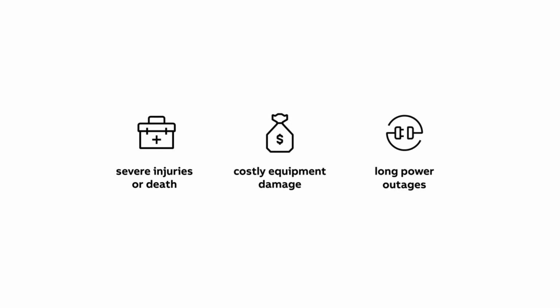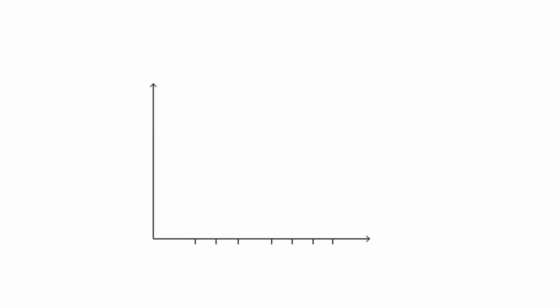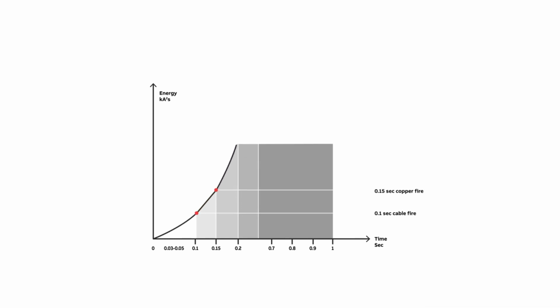and power systems. An arc flash can lead to severe injuries or even death, costly equipment damage, and long power outages. The main parameter of the electric arc, which characterizes its destructive ability, is incident energy. This is directly proportional to the arc duration and arc current. Without any active arc flash mitigation solutions in place, the arc clearing time may vary from 0.2 to 0.4 seconds. Within this short time, cable, copper, and steel can burn, melt, and vaporize. Therefore, it is of utmost importance to pay attention to arc flash protection.